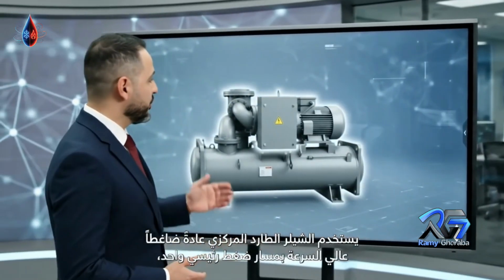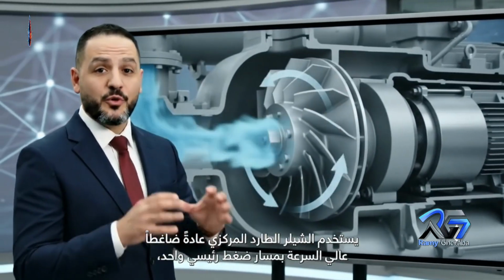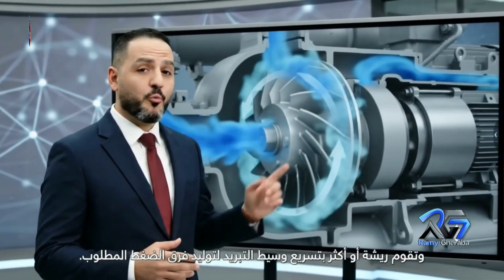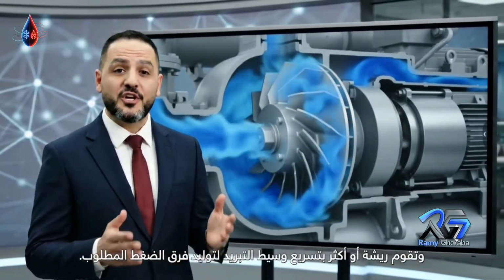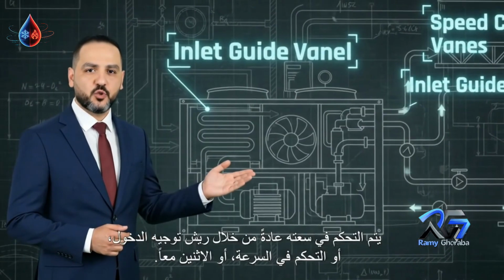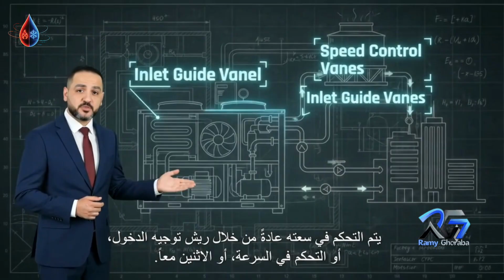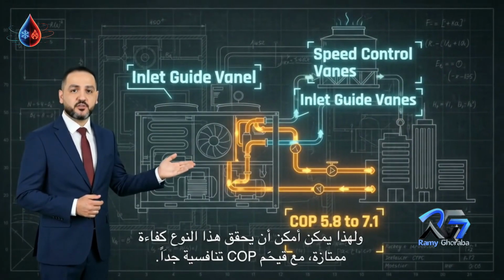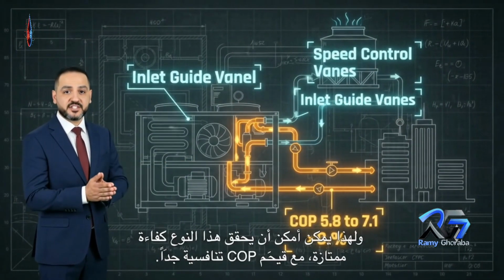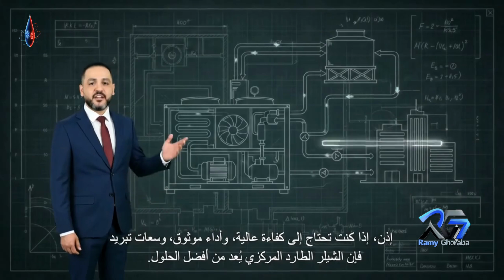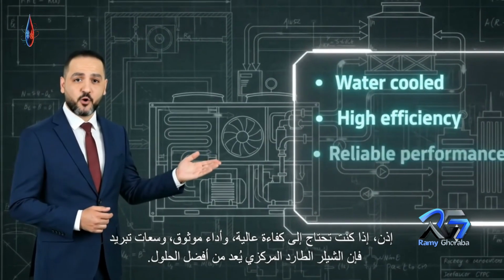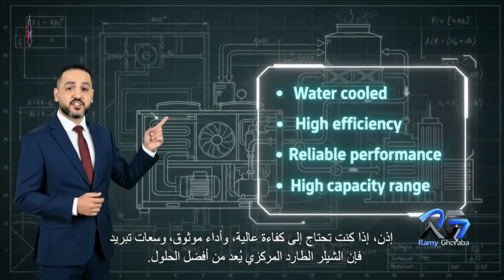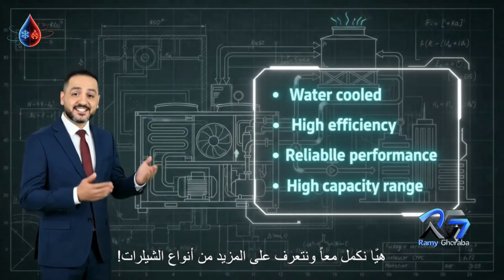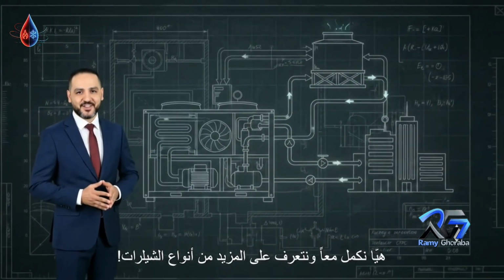A centrifugal chiller usually uses a high-speed compressor with one main compression train. One or more impellers accelerate the refrigerant to create the required pressure rise. Its capacity is commonly controlled by inlet guide vanes, variable speed control, or both. That is why centrifugal chillers can achieve excellent efficiency, with high COP values. So, if you need high efficiency, reliable performance, and large cooling capacity, the centrifugal chiller is a top solution. Let's continue and discover more chillers together.